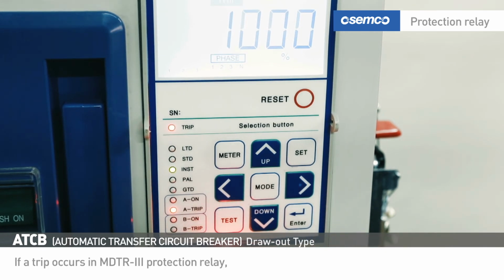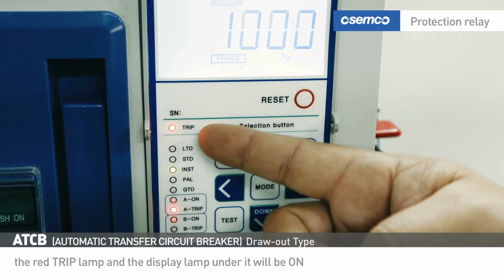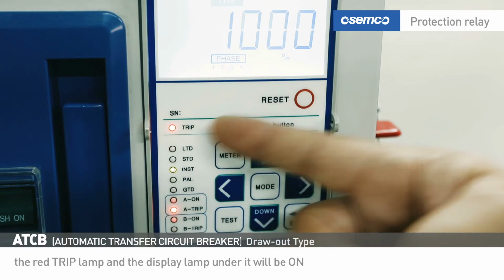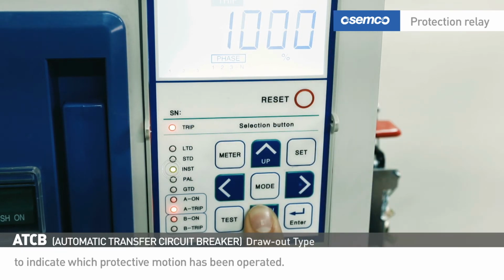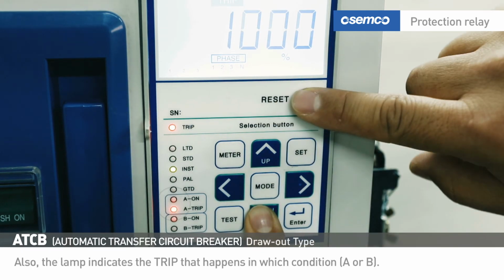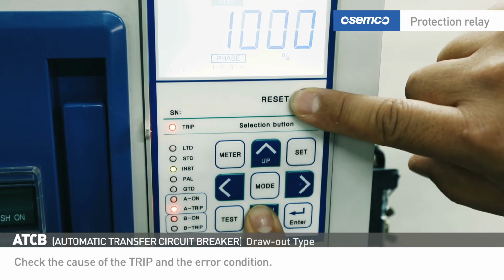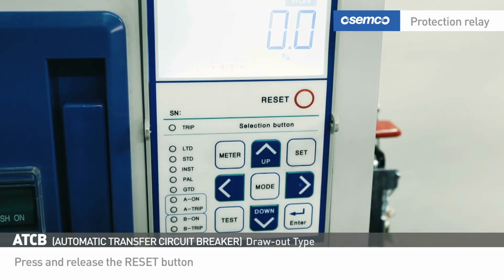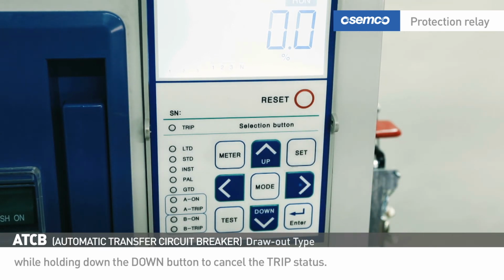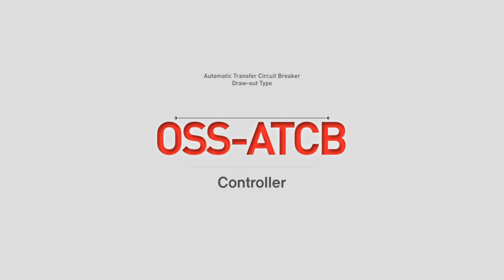If a trip occurs in MDTR3 protection relay, the red trip lamp and the display lamp under it will be on to indicate which protective motion has been operated. Also, the lamp indicates the trip that happens in which condition, A or B. Check the cause of the trip and the error condition. Press and release the reset button while holding down the down button to cancel the trip status.